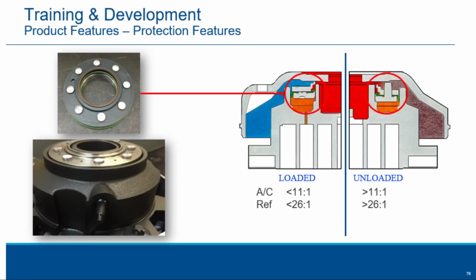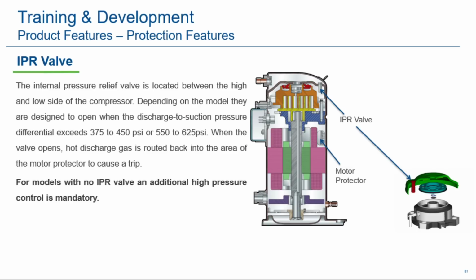Depending on the compressor, you'll have internal pressure relief, a temperature operating disc, or motor protectors. Internal pressure relief, I talked about it. Low pressure refrigerant will relieve at 375 to 450 differential. High pressure, like 410A, would be 550 to 625. That's the pressure differential to open that valve so it doesn't explode. For models with no IPR valve, an additional high pressure control is mandatory. Where would I find that information?